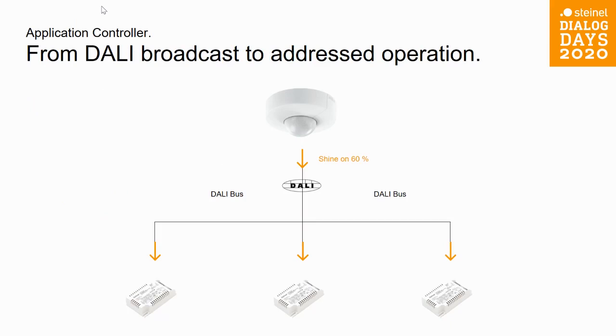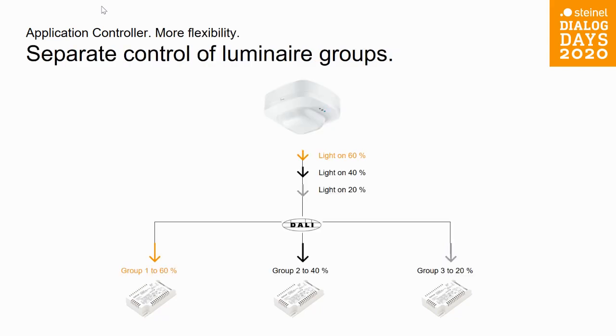So from DALI broadcast to the address operation. Traditionally, the broadcast sensors will send the light group to all groups connected. With the application controller, we have separate control of luminaire groups. So in this case, we have up to 3 groups connected from one sensor, and we are able to have different commands to different groups. In this case, we have group 1, the dim value is 60%, group 2, 40%, and group 3 at 20%, all from the same unit of sensor.